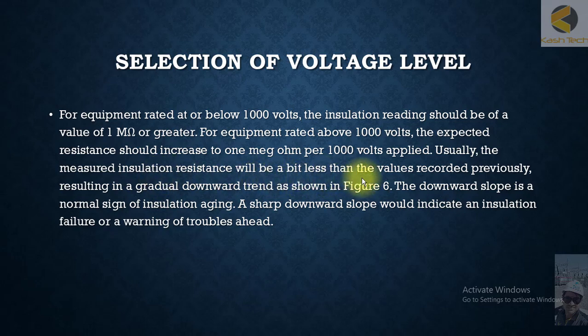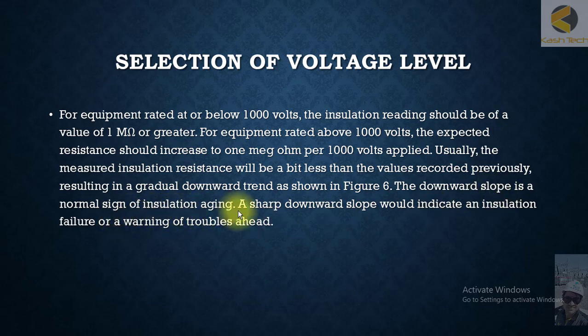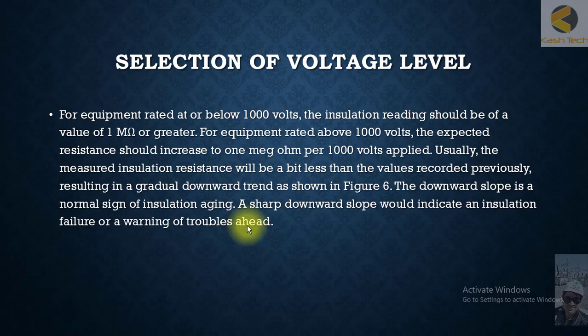The measured insulation resistance will usually be a bit less than the value recorded previously, resulting in a gradual downward trend as shown in figure 6. This downward slope is a normal sign of insulation aging. Since this is maintenance testing done every year, each year the insulation resistance will be slightly less than the previous year — a downward trend or pattern which is perfectly normal.